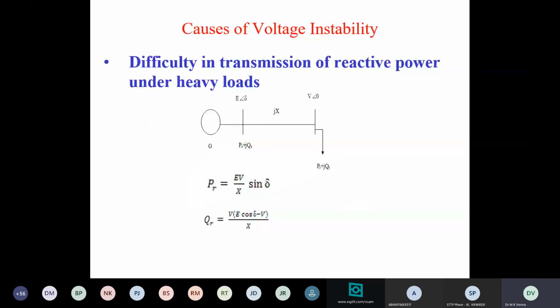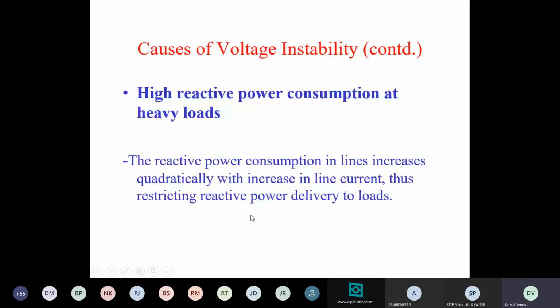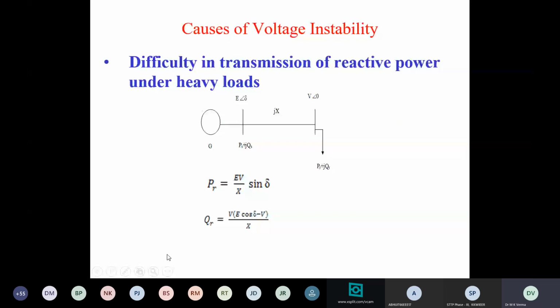There are different causes of voltage instability. One is difficulty in transmission of reactive power under heavy loads. We talk about this radial system, though the actual system is a large interconnected system. But in order to understand this, consider a two-bus radial system. The real power transmitted can be given by EV by X sin delta. Reactive power can be given as V E cos delta minus V squared by X. If demand increases, delta increases, and you are able to transmit real power. But with increasing delta, cos delta will decrease, and it is quite possible that QR becomes negative. If QR is negative, it means you are unable to transmit reactive power to the load. So you are not able to fulfill the reactive power requirement of the load, and that may cause voltage instability.